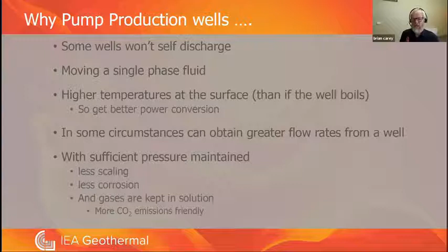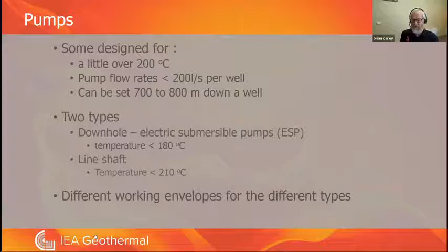A bit about pumps: some are designed for a little over 200 Celsius, with flow rates normally less than 200 litres per second per well or pump, and they can be set about 700 to 800 metres down a well. There are two types of pumps: electric submersible pumps, where the pump is down the well, and line shaft pumps, where the motor drives from the surface. Electric submersibles normally operate below 180 degrees Celsius, while line shaft pumps operate below 210 degrees Celsius, each with different working envelopes.